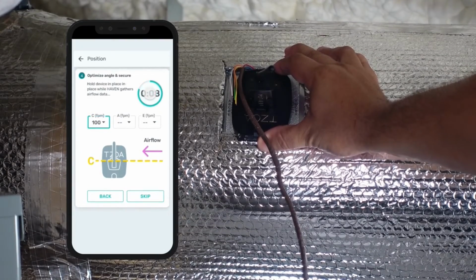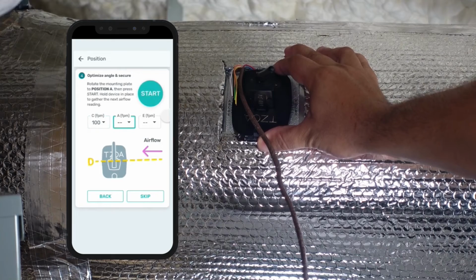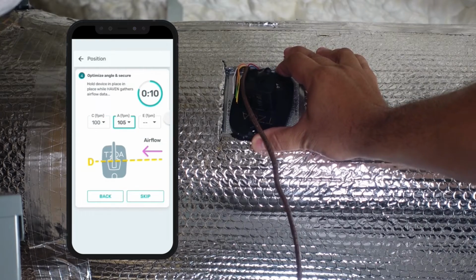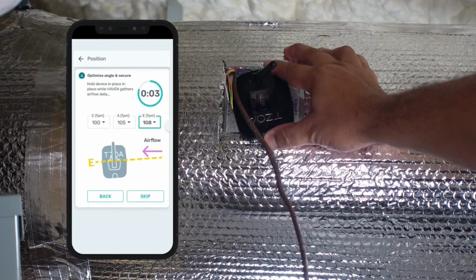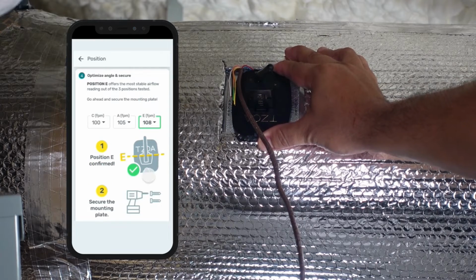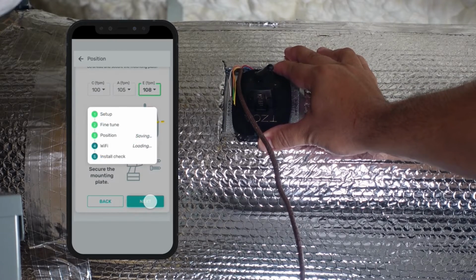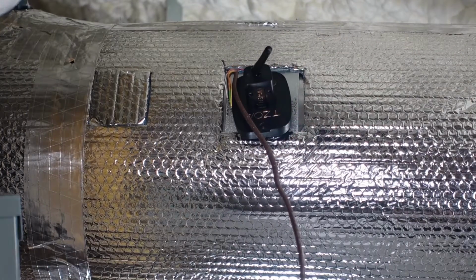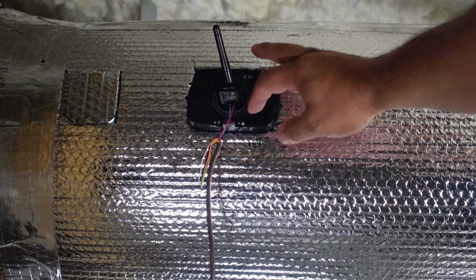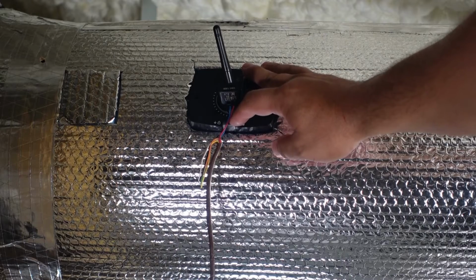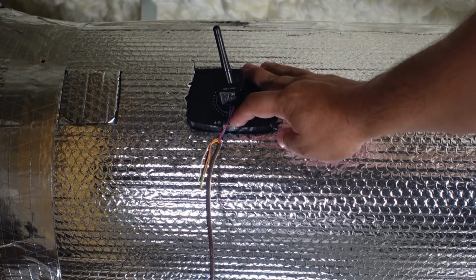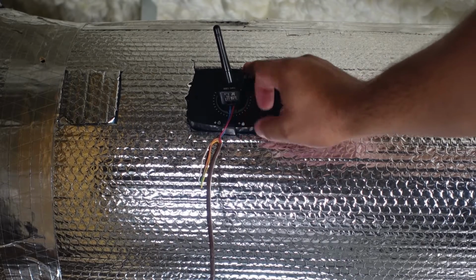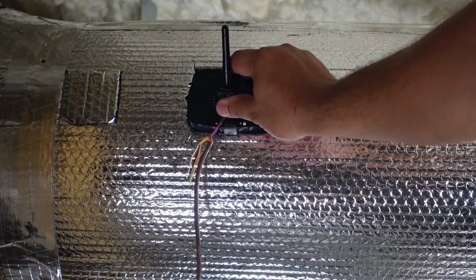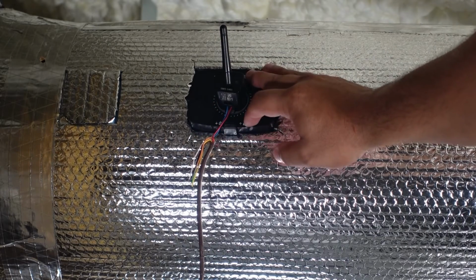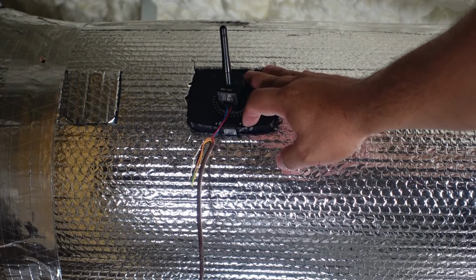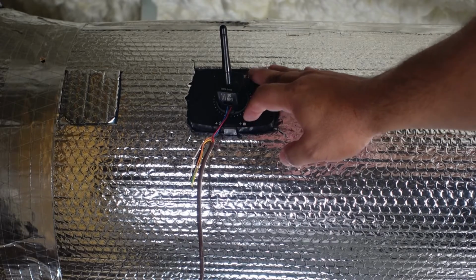If you have version 1, the non-rotating mounting plate, the app will prompt you to slowly rotate the mounting plate during the airflow optimization step, testing out a few different positions that are marked in the alignment plate. If you have the rotating mounting plate, it should be secured already at this point. You can simply pull down the locking tab and rotate the probe to match the instructions on the app. This step helps to determine the optimal angle for airflow, which is required for accurate particle readings.